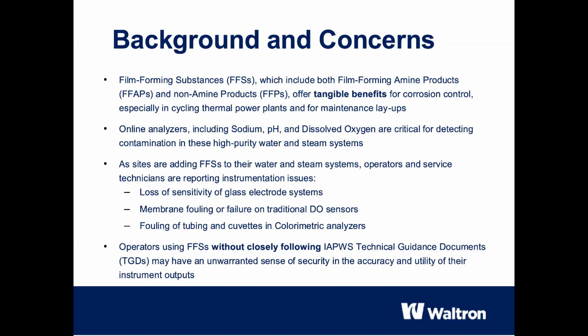Although the IAPWS has published several technical guidance documents, TGDs, on this topic, many operators are still unaware of the potential problems. The biggest danger here is a false sense of security. When an operator looks at an analyzer that shows stable values, they assume the plant's water chemistry is safe. But what if the device is being blinded by the same chemistry designed to protect the plant? This is precisely the question we wanted to answer.